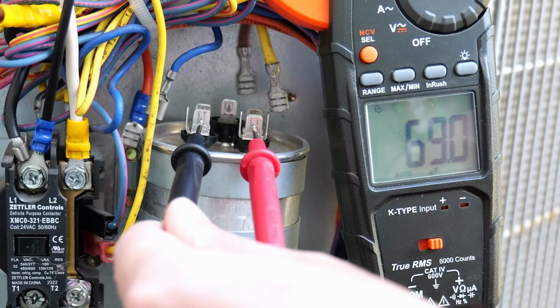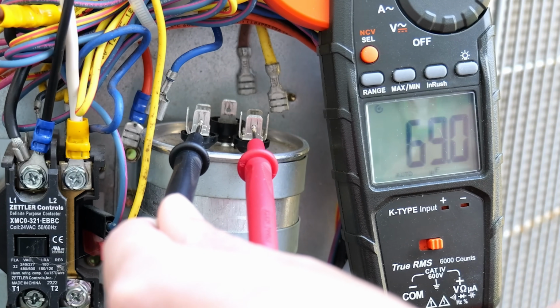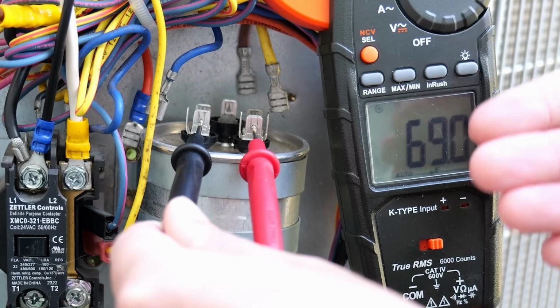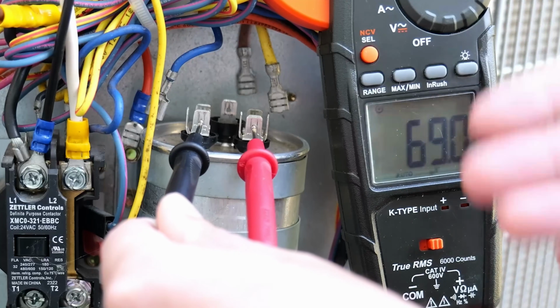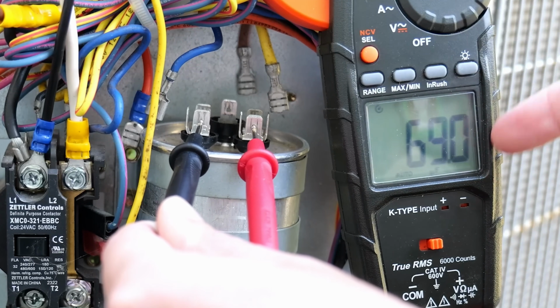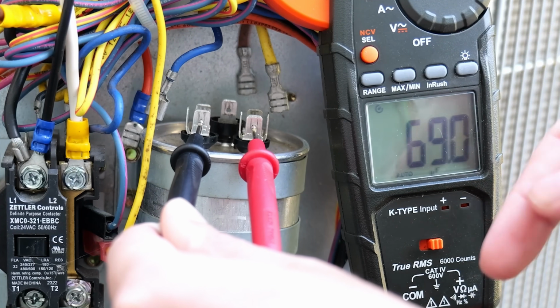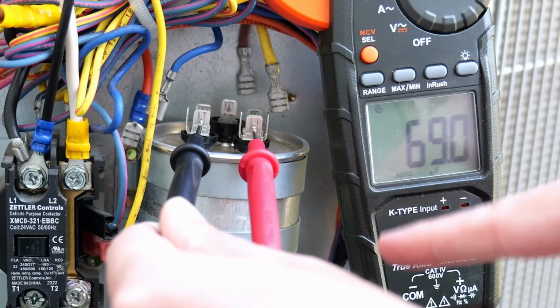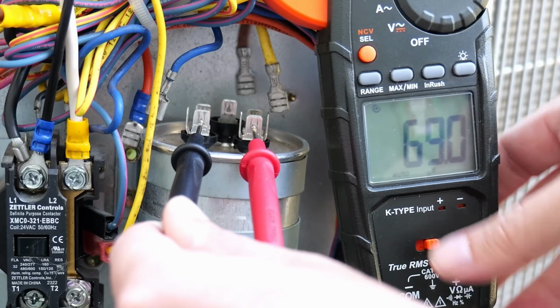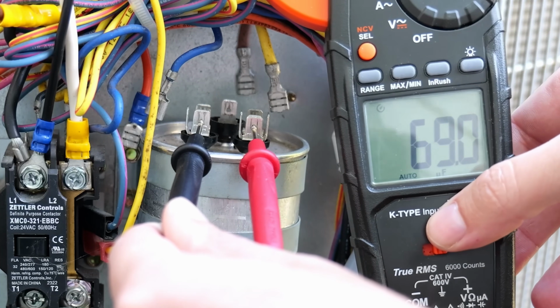That is well within the 6% of that 70 microfarads that we need to have. At 70 microfarads, to get within 6% plus or minus, that would be about 4 microfarads low or high. We're only 1 below the 70. So from the common to the herm side, that part of the capacitor is showing that it is still in good condition. So now I'm going to check the fan reading.